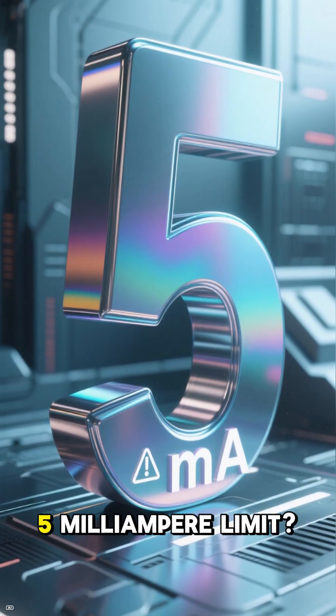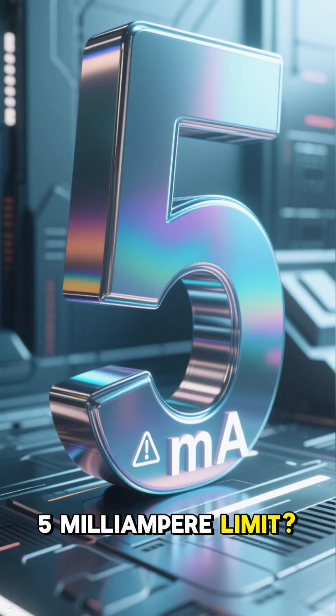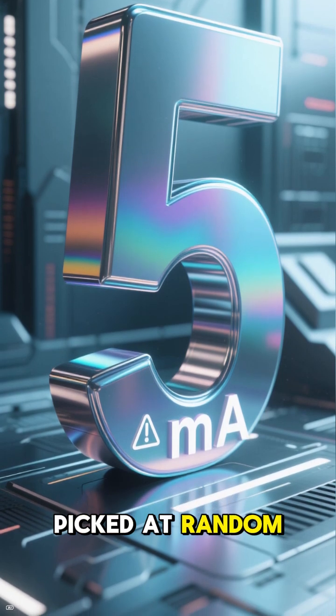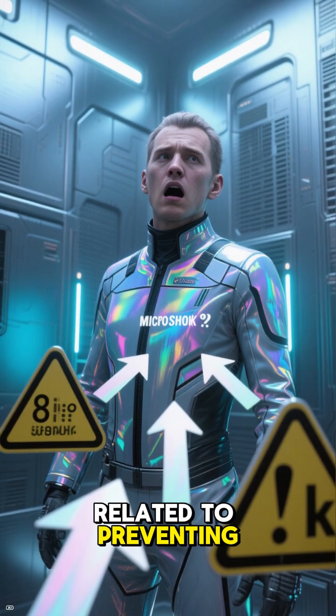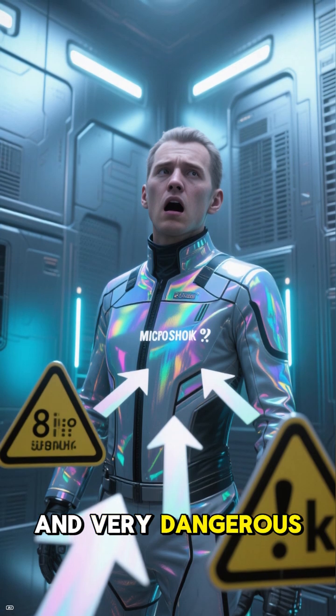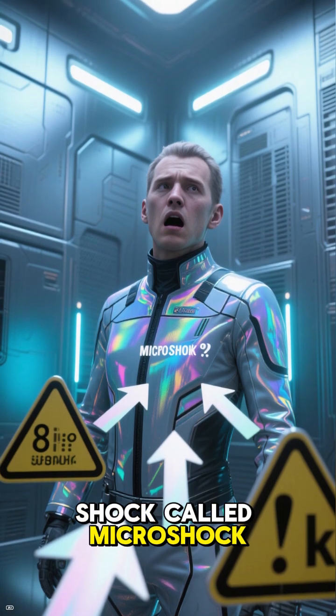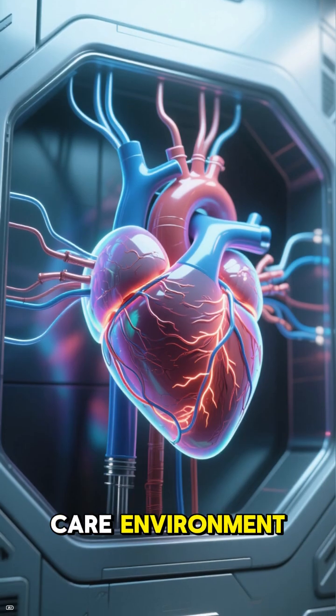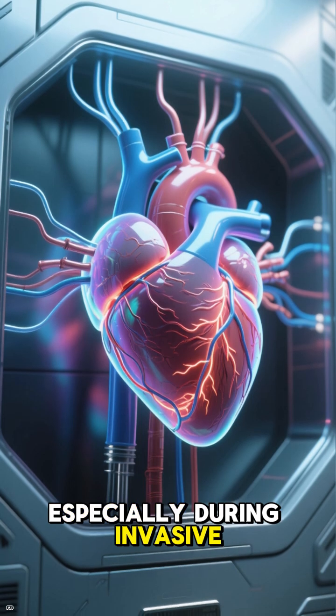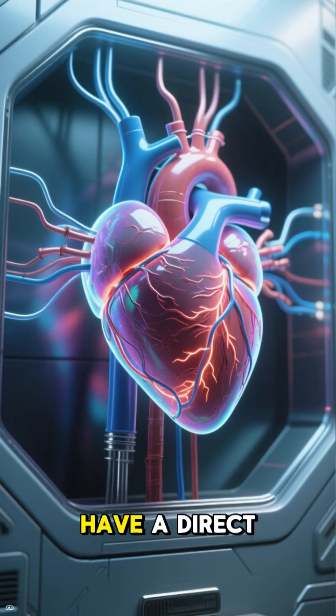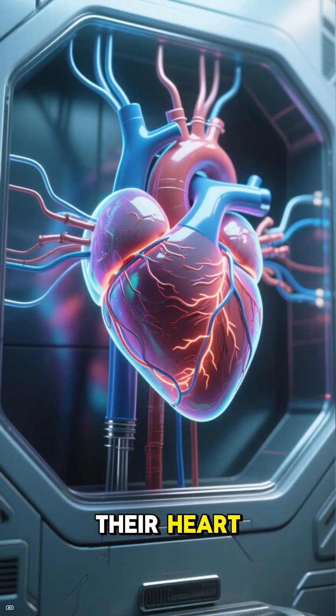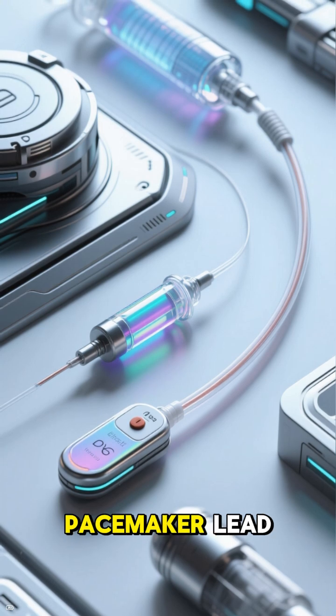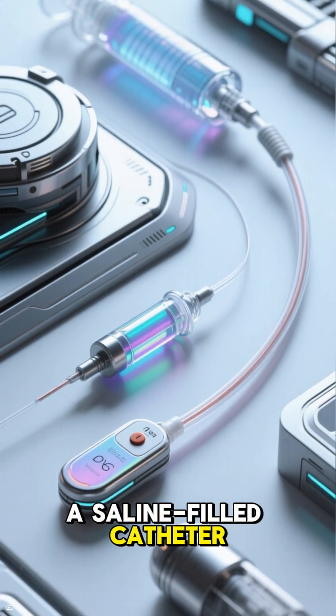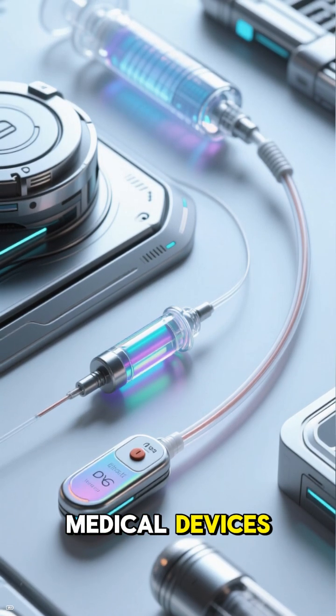So, why the 5 milliampere limit? This number wasn't picked at random. It's directly related to preventing a specific and very dangerous type of electric shock called microshock. In a patient care environment, especially during invasive procedures, a patient might have a direct electrical path to their heart. This could be through a pacemaker lead, a saline-filled catheter, or other conductive medical devices.